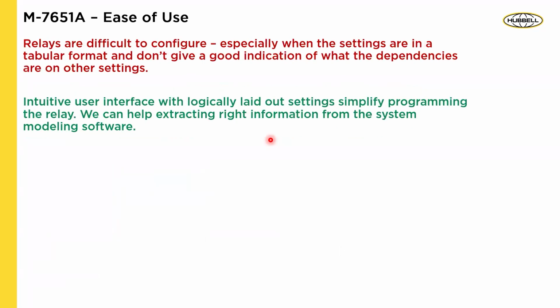And what we hear is as newer and newer generation of engineers come in, the relays seem difficult to configure, especially when settings are in tabular format and you don't know if a setting has a dependency on another setting, right? So what we've done is we've intuitively made the interface in such a way that your settings are grouped in a logical way, right? So you know that the pickup value and the time dial, and the minimum response time, those are the settings that go together. Now, voltage supervision that you do, that could be a separate group, right? So we're not going to just put it one after the other and let you figure it out. We make it easy for you to go in and do that.